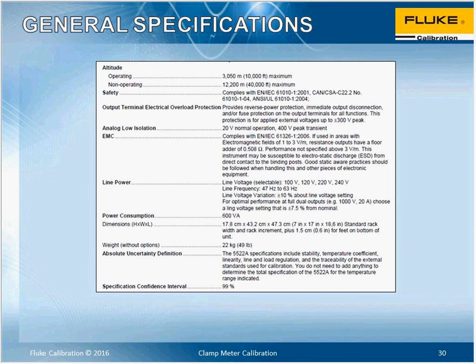Also, EMC. This goes into EMC and line power, and I combine those sometimes because what you want to make sure is if you have any voltage spikes, or your power is interrupted, or a lightning strike occurs, is it going to damage my calibrator? Products out there have good line power handling for spikes, but you want to make sure it can handle all of that, or you're going to find yourself in a calibration where a spike ruins the calibrator, especially when you're using high voltage or high current out of it.